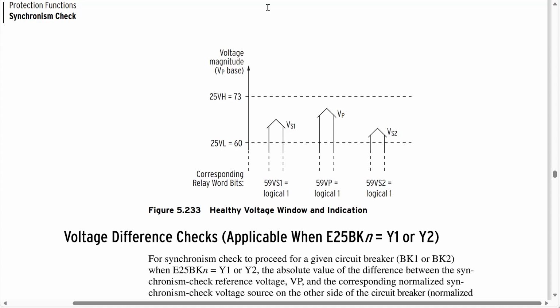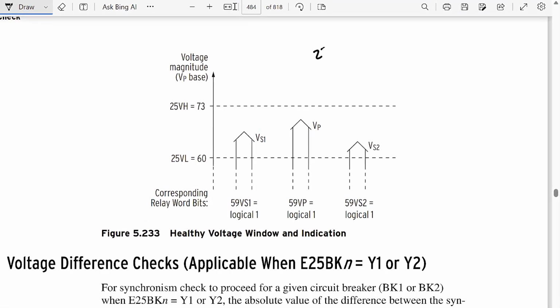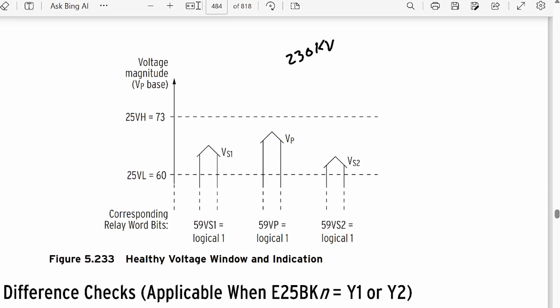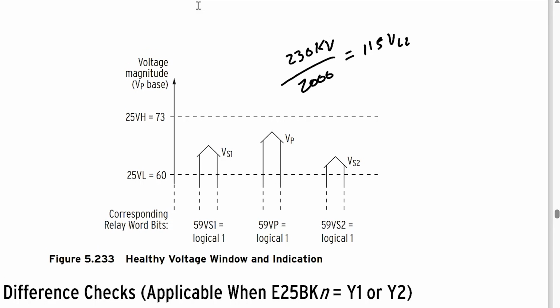Now, this is why I mentioned before that it's important that we also calculate the phase to neutral voltage, because again, we're comparing the A phase to neutral voltage from the line side to the A phase to neutral voltage from the bus side. Both of those are phase to neutral voltage, not phase to phase voltages. So again, if we have a 230 kV nominal transmission line, that voltage is line to line. We can divide that by 2000. That gives us that the nominal voltage in the secondary of the PTs line to line is 115. Now we have to divide that, of course, by square root of 3 to get the line to neutral voltage. And that gives us that the nominal line to neutral voltage is 66.4 volts line to neutral.